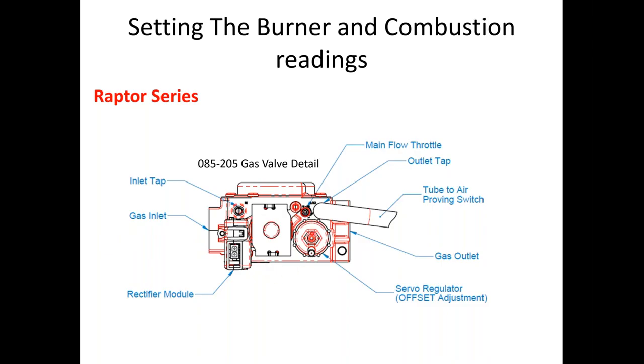On the other hand, the offset regulator, you barely want to move that. A 1/8 of a turn, or barely even an 1/8 of a turn, you get a lot of movement out of it. If you move it too much, the gas valve gets way out of whack and we usually lose the low fire feature. Unfortunately, when that happens, that's a new gas valve. In some cases, I've had contractors get confused and go to turn the regulator to bottom it out for the fuel adjustments. When that's done, the little diaphragm in here pops and the boiler will not run in low fire, and your high fire combustion numbers will be all over the place. You won't be able to get them to dial in. Right here is our rectifier module.